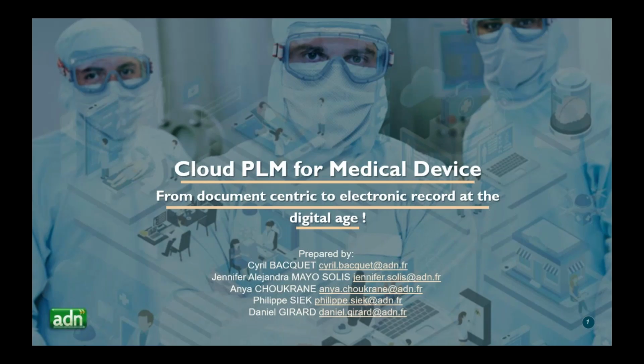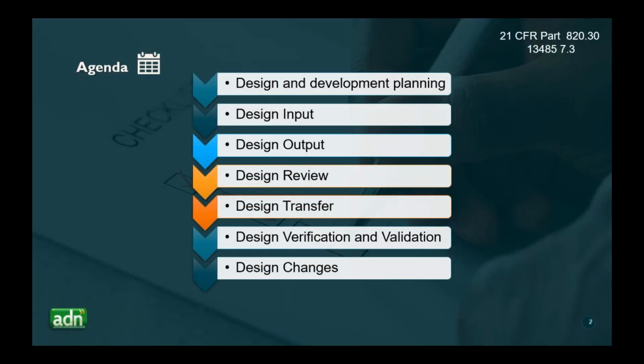Our cloud PLM for medical device goes from document-centric to electronic record in the digital age. So we're going to follow the different stages available in the 13485 norm. The stages are design and development planning, design input, design output, design review, design transfer, design verification and validation, as well as design changes. So let's start with the design and development planning.